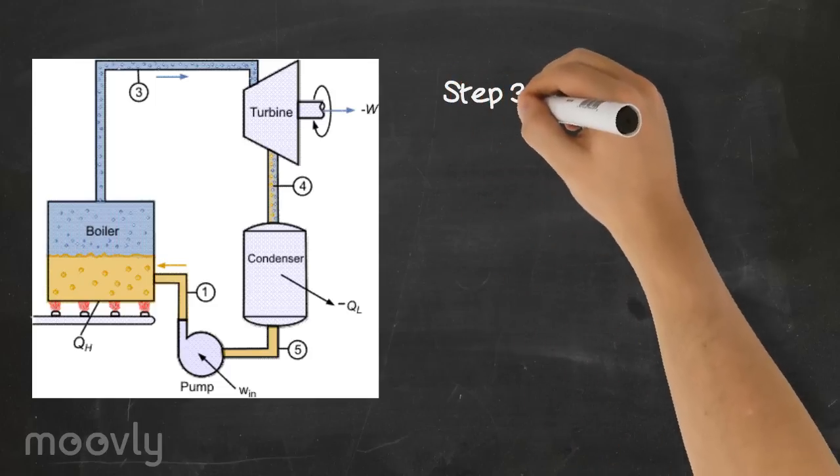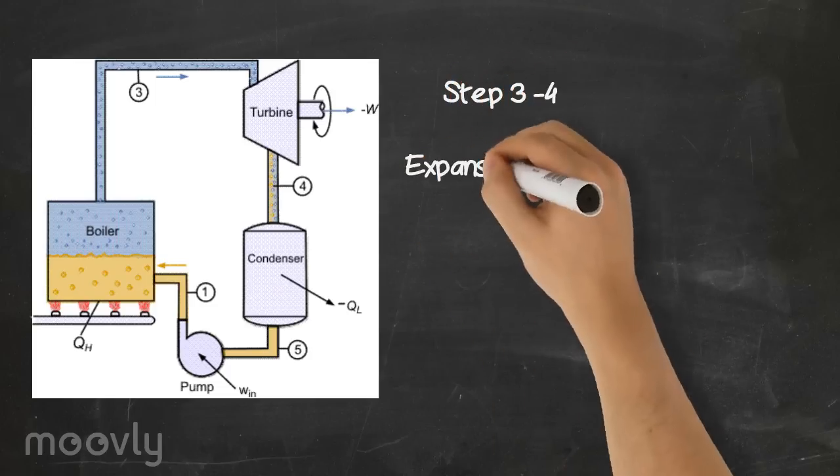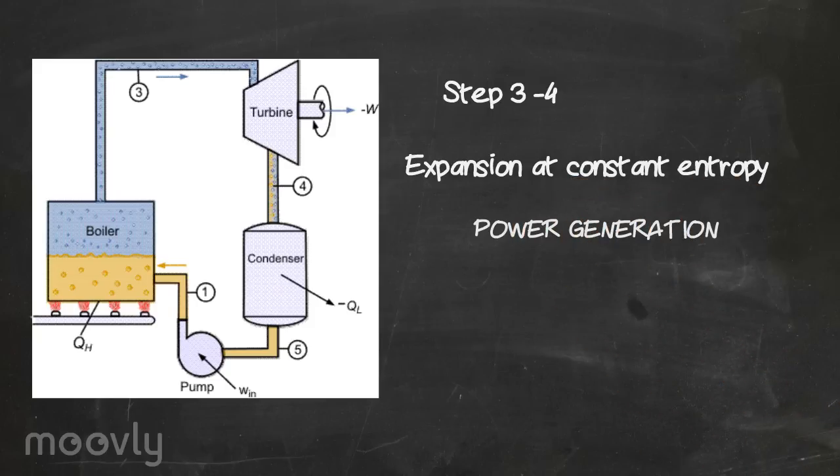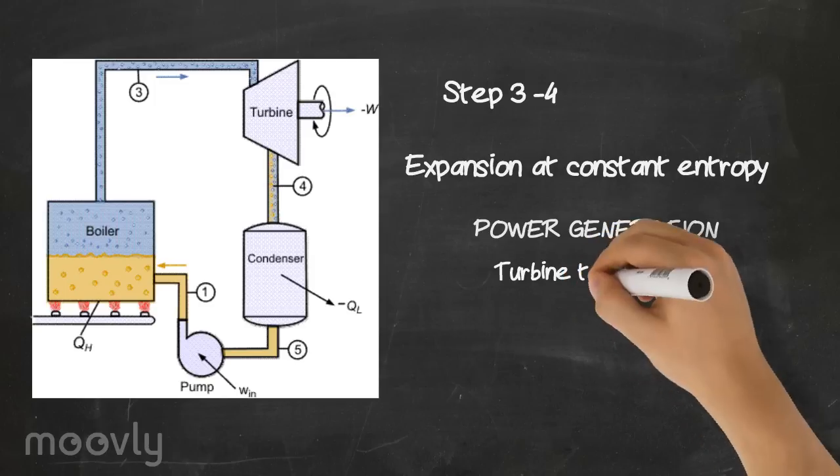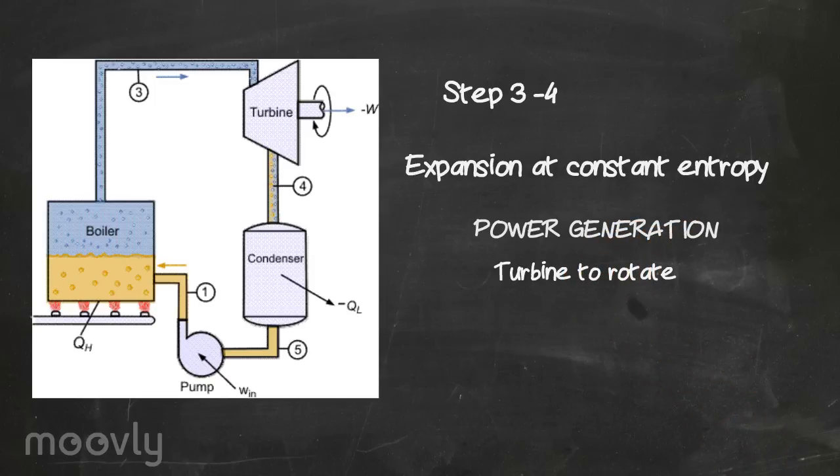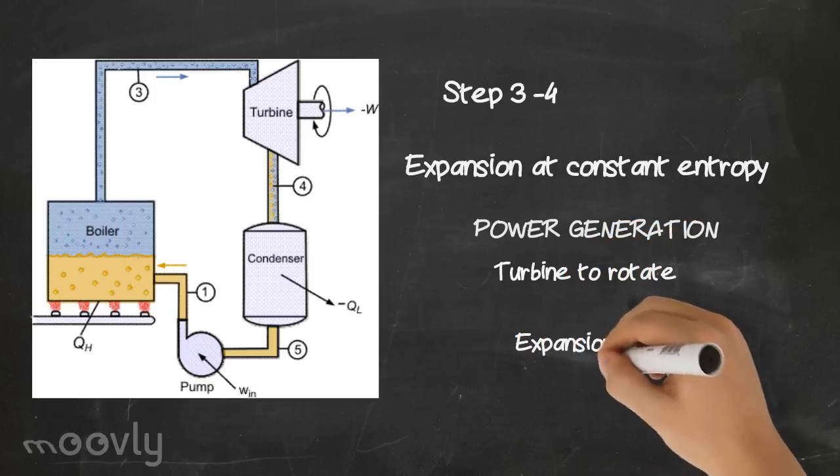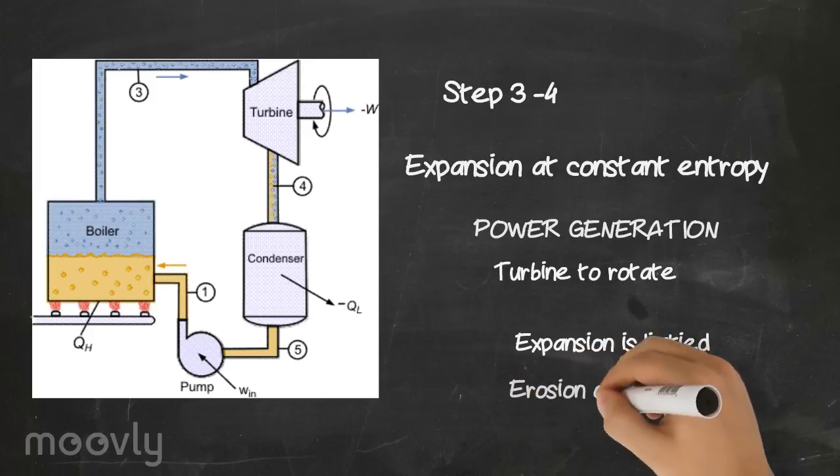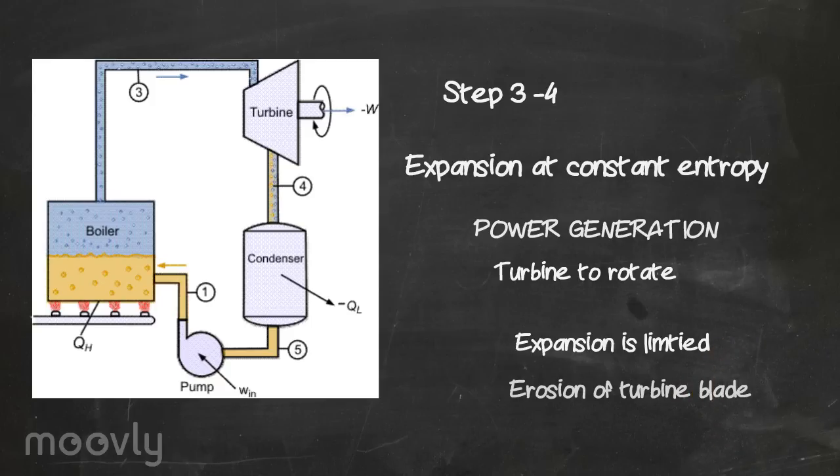Now, step 3 to 4, expansion occurs at constant entropy. This is the key step in power generation. The expansion of gas causes the turbine to rotate, thereby creating mechanical work from thermal energy. In practice, the expansion is limited by the temperature of the cooling medium and the erosion of the turbine blades. Exit vapor qualities should be greater than 90%. Note in the TS diagram, the entropy is constant.